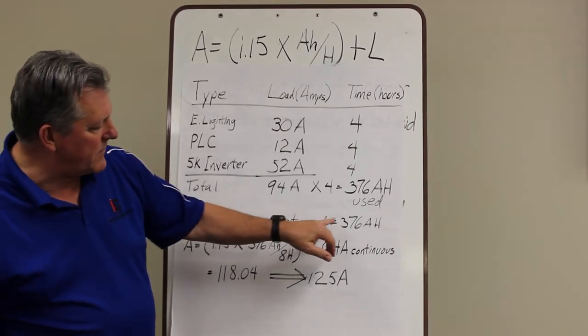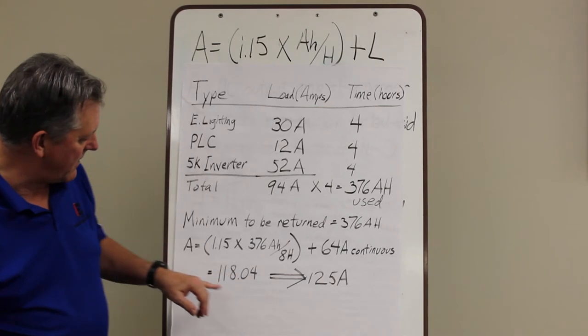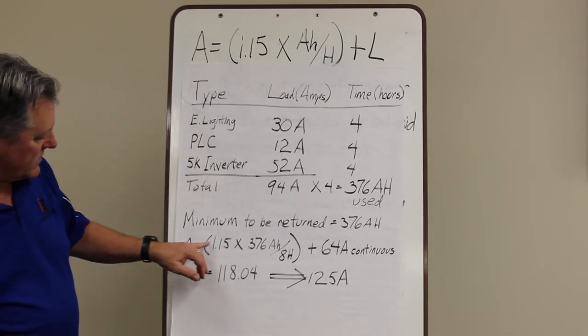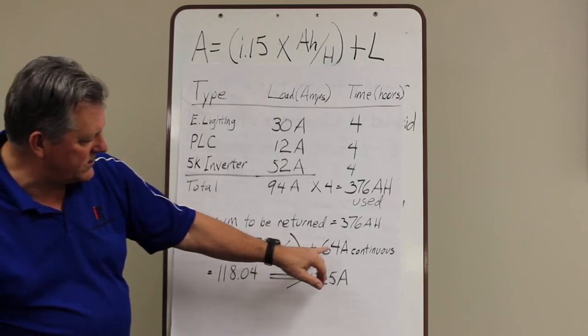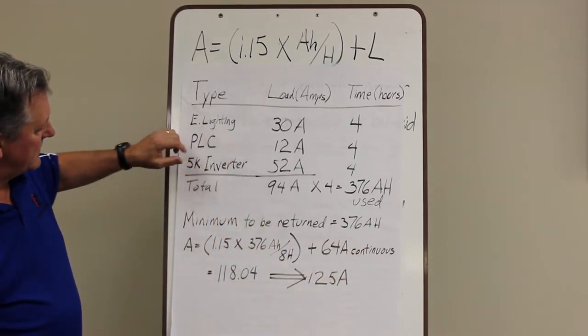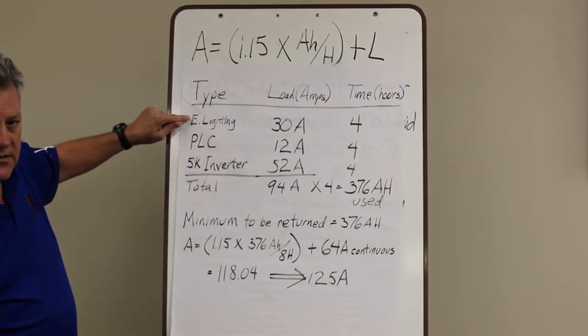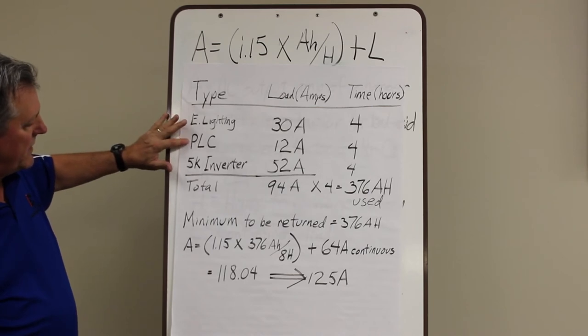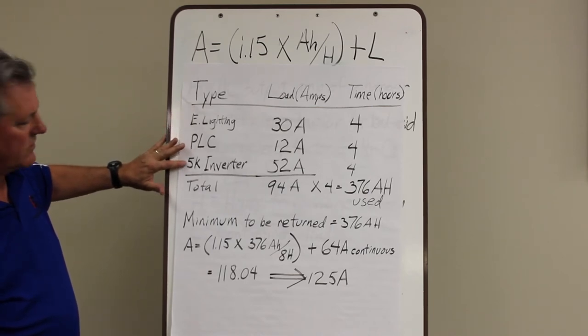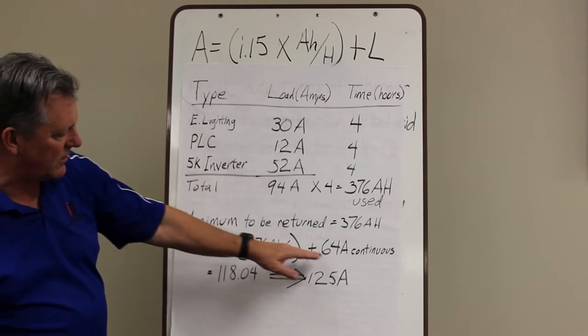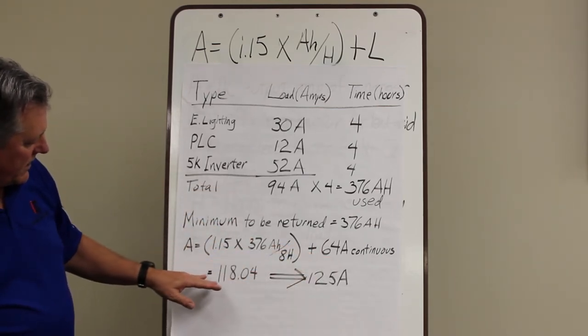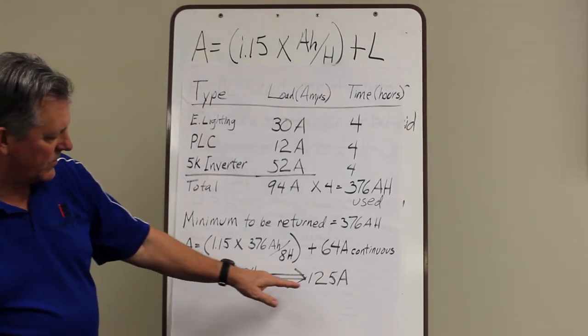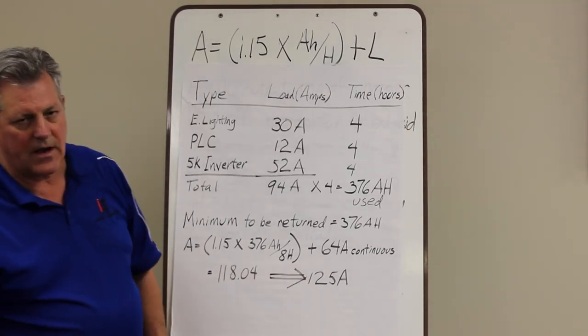So the minimum we have to return to that battery is 376 amp hours. So we take A equals 1.15 times 376 amp hours divided by 8 plus 64 amps continuous load. Now we get the continuous load. The emergency lighting is not being used on a continuous basis. The only thing continuously load would be the PLCs and the 5K inverter. So those together would come up with 64 amps continuous. So we run through that equation we get 118.04 amps which is the next size up is 125 amp charger. It's a pretty simple equation.